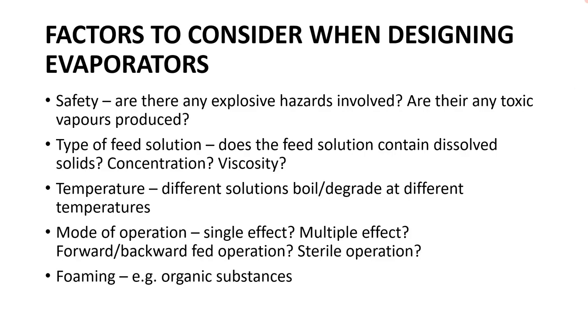Another extremely important factor to consider is the type of solution being evaporated. For example, if the solution contains dissolved solids, the liquor produced in the evaporator may become saturated and form crystals. This can be a big problem because if not cleaned out properly, scale can be formed, which can reduce the overall heat transfer coefficient as well as potentially clogging up the evaporator. The concentration and viscosity of the feed solution will also need to be considered.